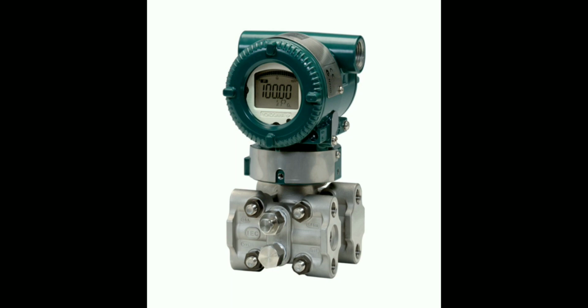Disadvantages of a gauge pressure transmitter. Change in altitude can impact the gauge pressure reading, as atmospheric pressure decreases with elevation. In high altitude locations, adjustments may be required. Atmospheric pressure is influenced by weather conditions, leading to potential variation in gauge pressure readings. Weather changes may require adjustments for critical applications. Gauge pressure does not provide information about the absolute pressure in the system. In some processes, knowing the absolute pressure is essential.